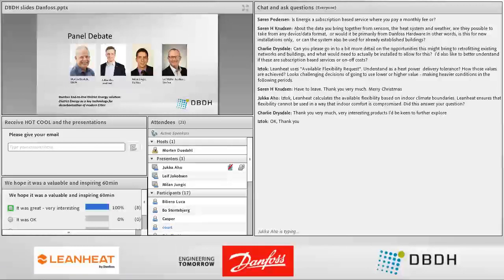It's a combination of many things, of course, but what is important, I mentioned it shortly also during my presentation, is that you need to have a good load forecast. That's very important, and we have a very strong and robust one in Mentor Planner. And if you have that, that's important, and also because you need to look ahead. It's too late if you just use the outdoor temperature and base it on that, because that's too late.